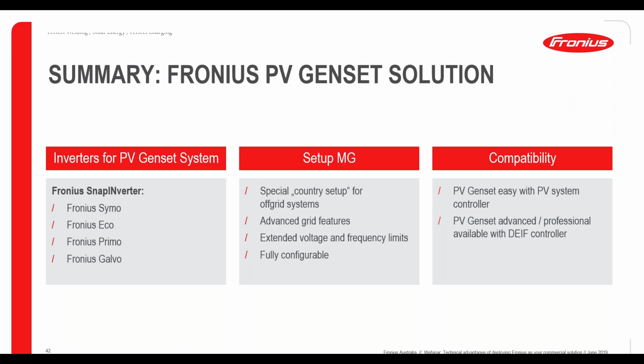I just wanted to add something a little bit. The PV-Genset Easy Controller, in my opinion, has become an even more interesting option because petrol and diesel prices are just increasing as time goes by, especially for those regional customers with irrigation. It can present itself as a unique, easy solution because, as in the graph we saw before, you only need one controller and the inverters to make it work. Bear in mind, an inverter is a current source, so it needs a voltage reference point in order to function properly, which in this case is provided by the generator. But if you think about it in terms of energy flow, and especially the ease of deploying this solution, it can be a unique solution going forward for small to even medium commercial systems, where cost saving is the primary driver, and simplicity as well. Yeah, that's a bit extra to that.